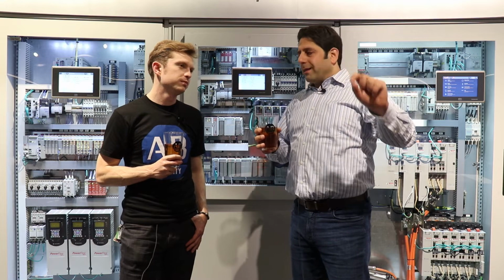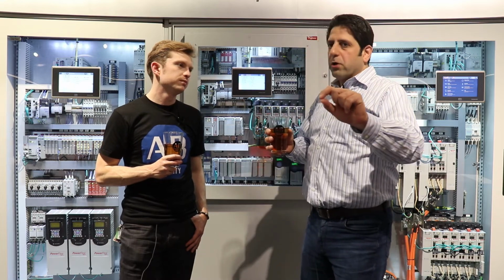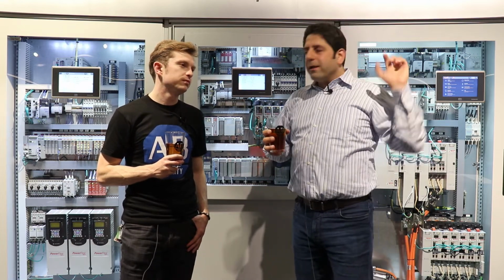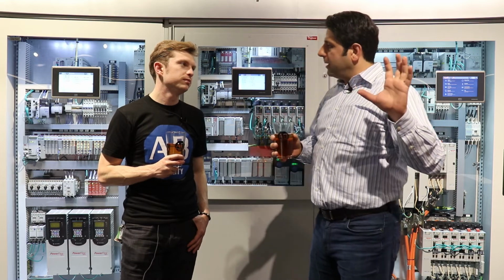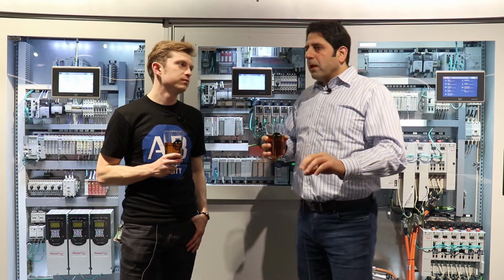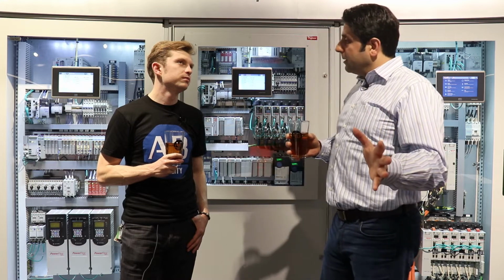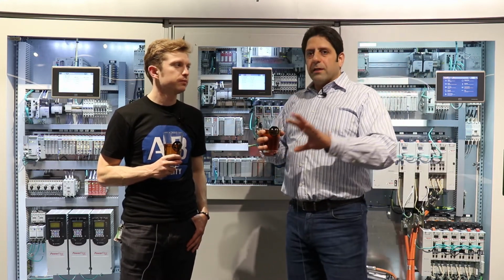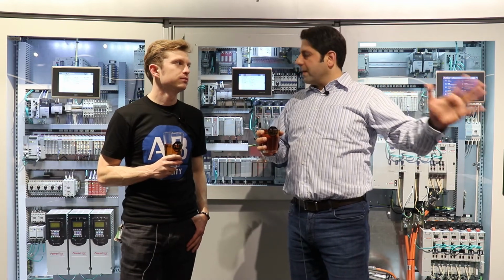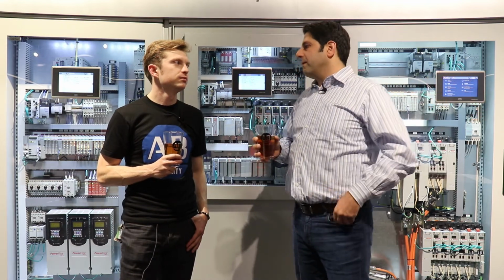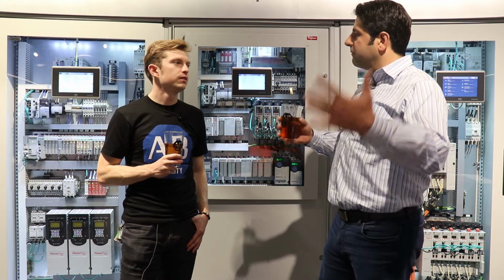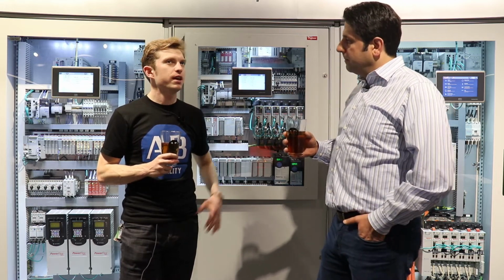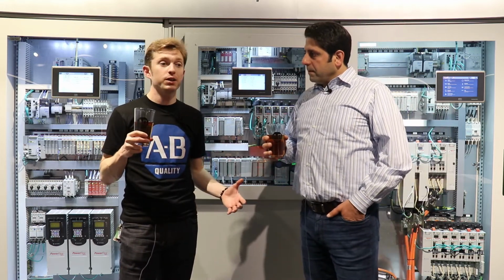Once we reach that Logix controller, TeamONE is able to go through the backplane and hop another network. That other network could be a private Ethernet network. It could be legacy networks like Data Highway Plus. It could be a ControlNet network that will eventually get us to another Logix chassis, will get to the backplane, and then talk to that maybe older controller like a 1756 L63. Sure. So that's quite a range that we're talking about.